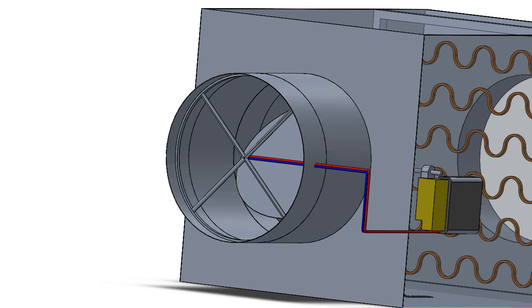You can find the differential pressure across the device. And if you average that for the size of the duct and calibrate it a bit, then you can calculate the flow rate of air entering into that box and zone.